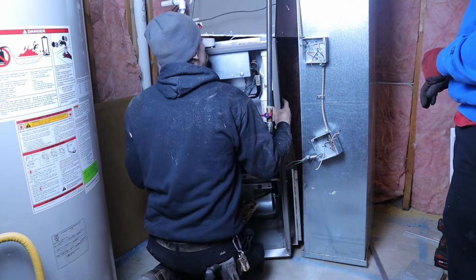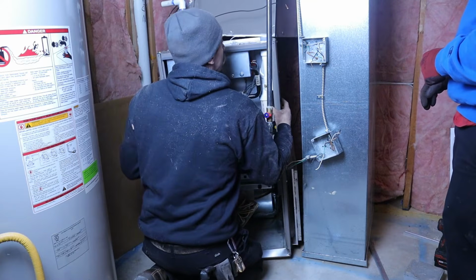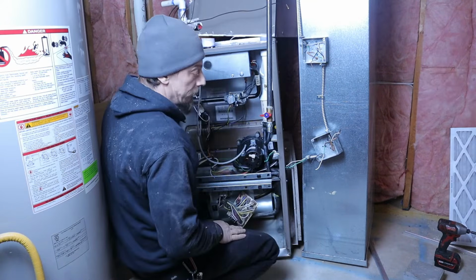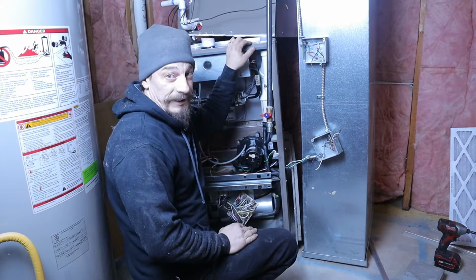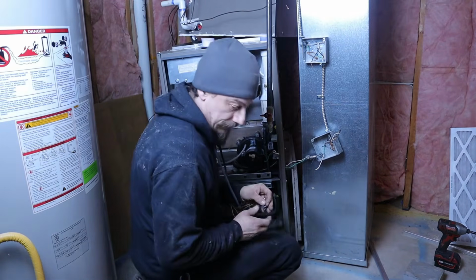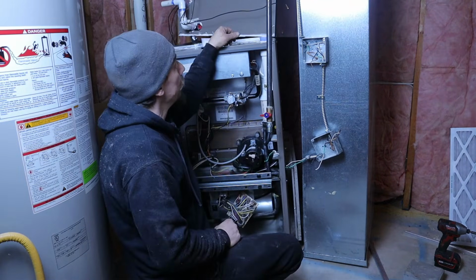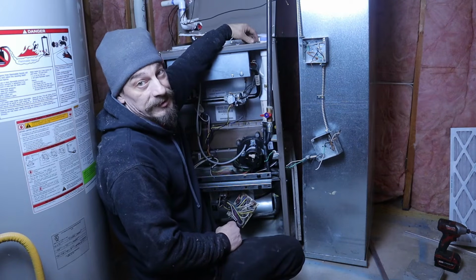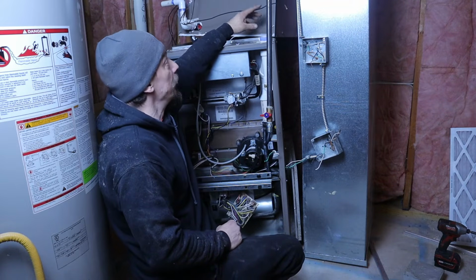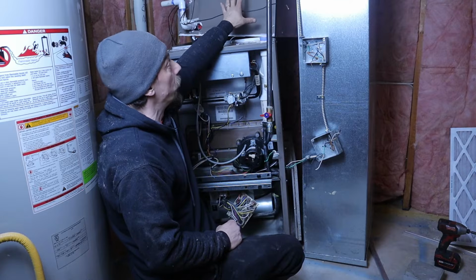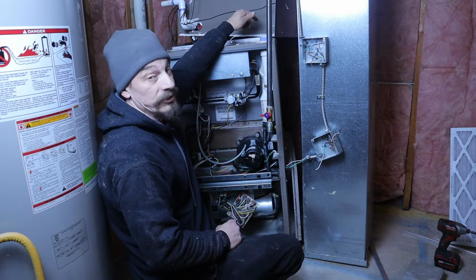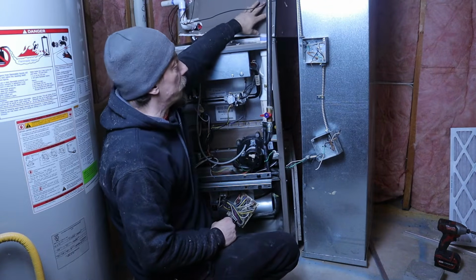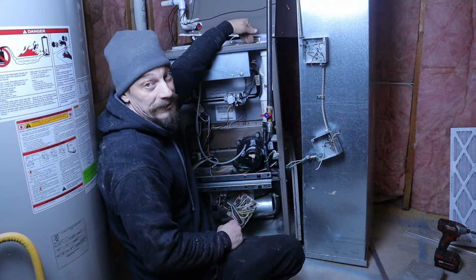They got a screw in there. Sold on. Yeah, they screwed it from the inside. All right, so what these guys did when they originally installed this furnace is they had the coil out and they screwed the casing of the coil to the furnace from the inside.